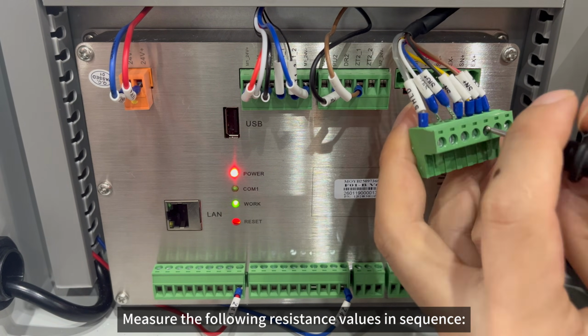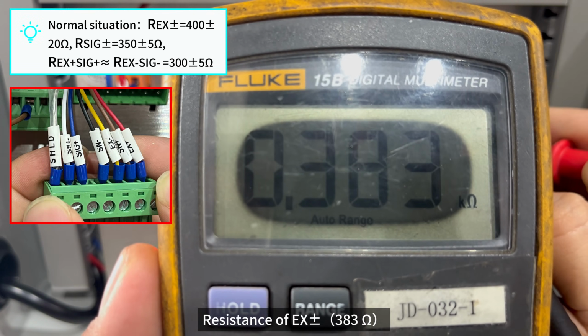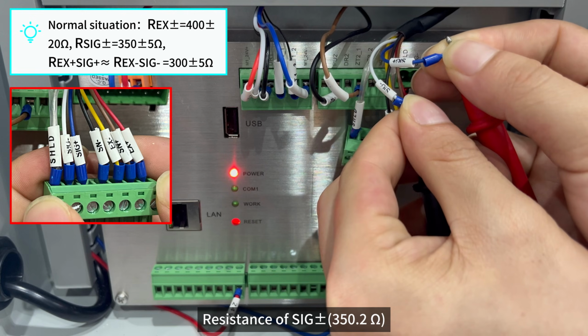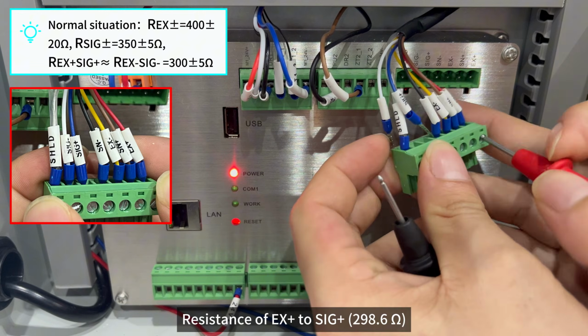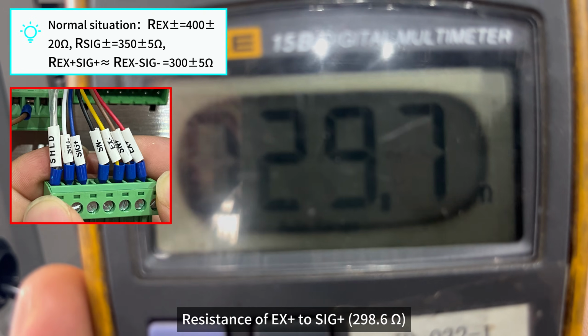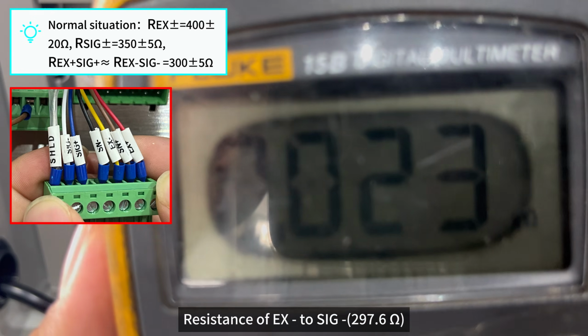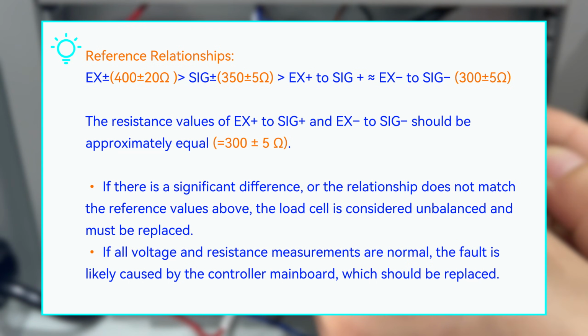Measure the following resistance values in sequence: resistance of EX plus and minus, resistance of SIG plus and minus, resistance of EX plus to SIG plus, resistance of EX minus to SIG minus. Reference relationships: EX plus and minus greater than SIG plus and minus greater than EX plus to SIG plus, EX minus to SIG minus. The resistance values of X plus to SIG plus and X minus to SIG minus should be approximately equal. If there is a significant difference, or the relationship does not match the reference values above, the load cell is considered unbalanced and must be replaced.